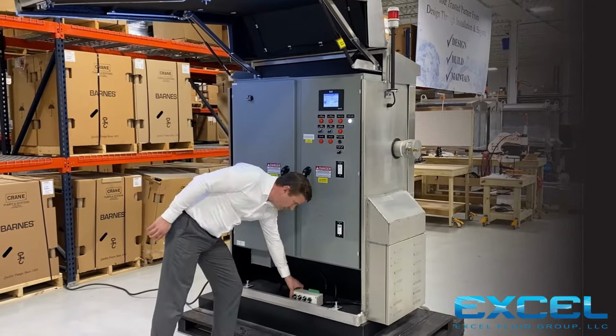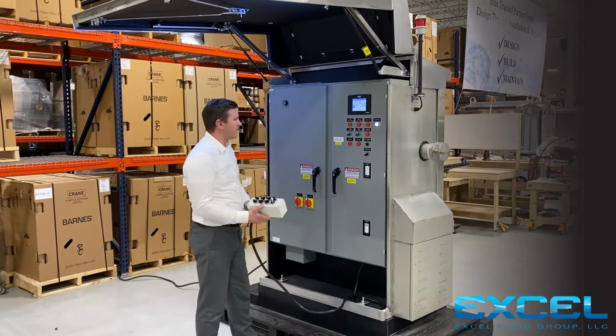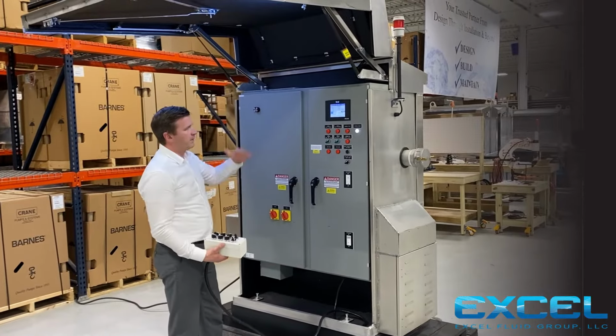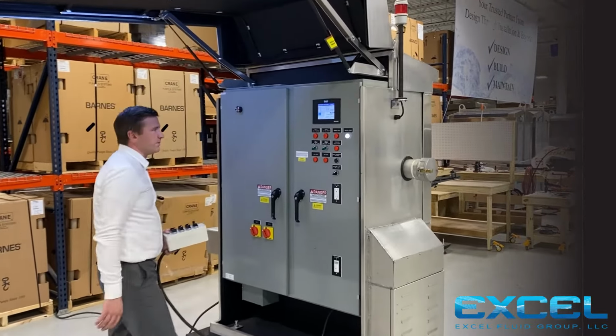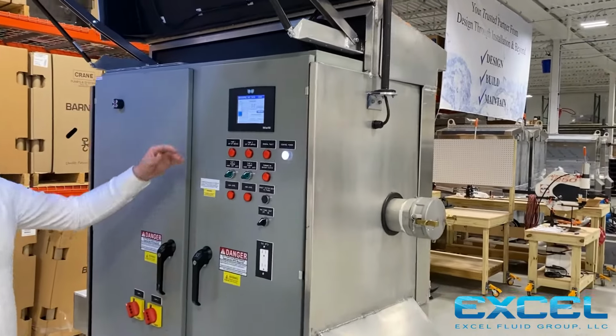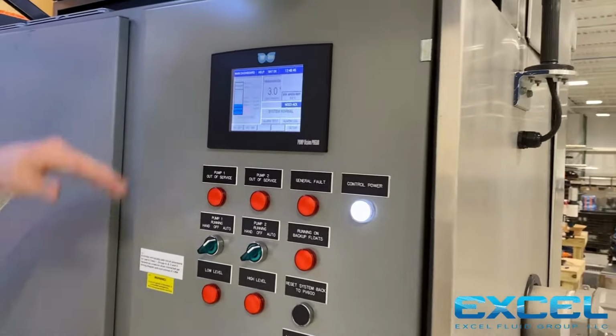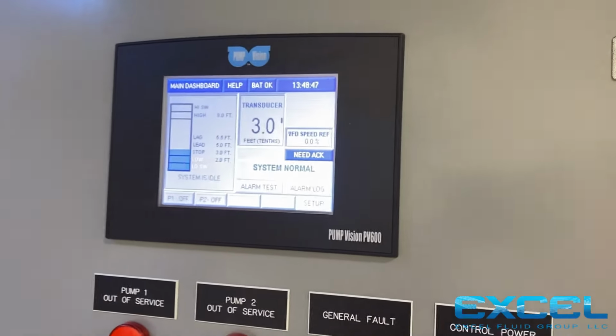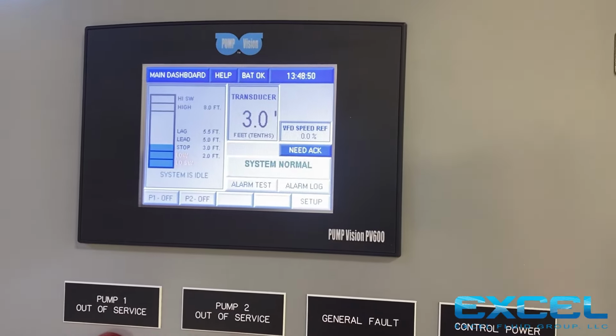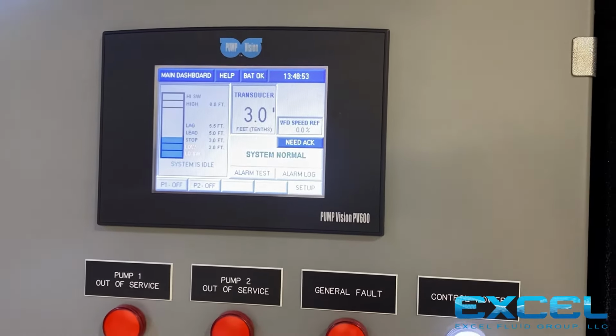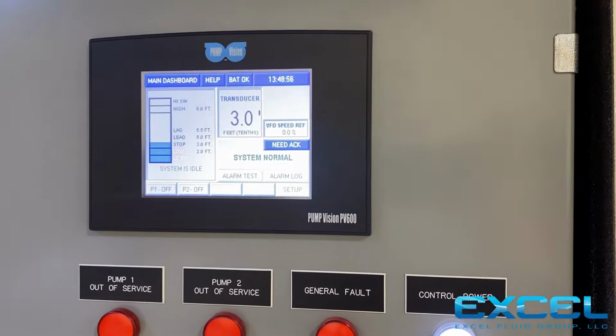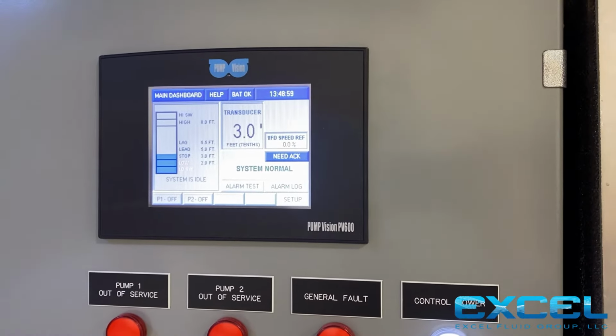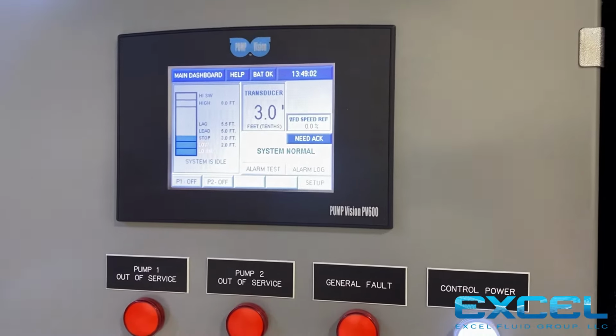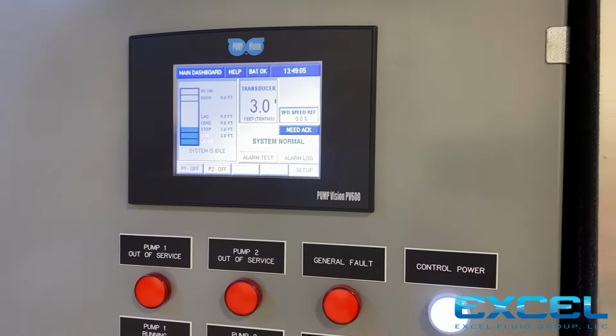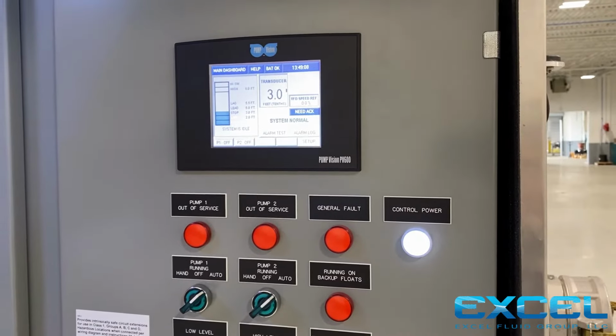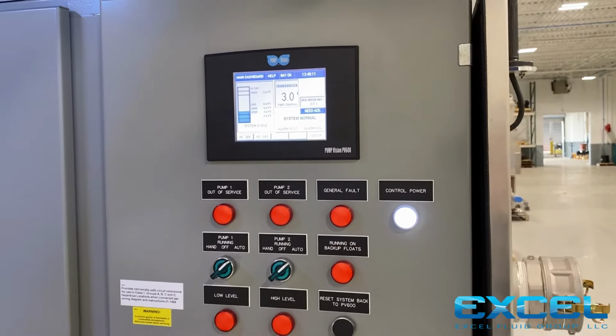I'm going to simulate with the simulation. This wouldn't typically be part of the pump station, but for the demonstration unit, I can show you as levels go up and down. Let's take a look at the controls. It's currently set in the demo unit to have its stop point at 3 feet. It's going to bring pump 1 on at 5 feet. If that doesn't bring level down, it brings pump 2 on at 5.5 feet. And finally, we get to a high water alarm point. It's fully float back, full redundancy with float backup. So in the event of a transducer fail or a complete PLC failure, it will call for float backup that will bypass both those into the relays and bring those pumps on to keep the station operating properly.